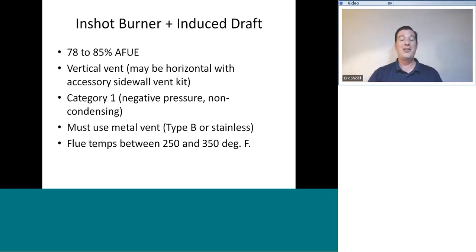As long as the manufacturer has specifically said that this is the sidewall vent kit part number to use and you use that one, then you're okay. But if you decide to take it upon yourself to invent a new venting system, that's not okay and that is not approved. So make sure you're reading the instructions on the furnace you're looking at. Not everybody follows those rules.